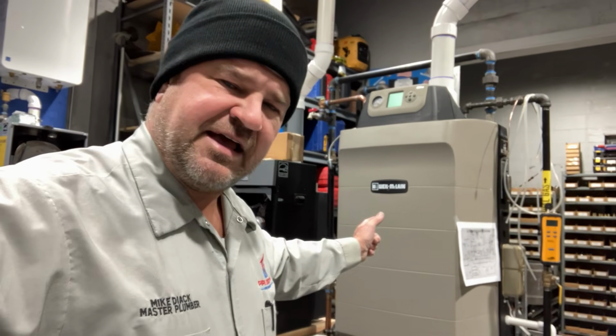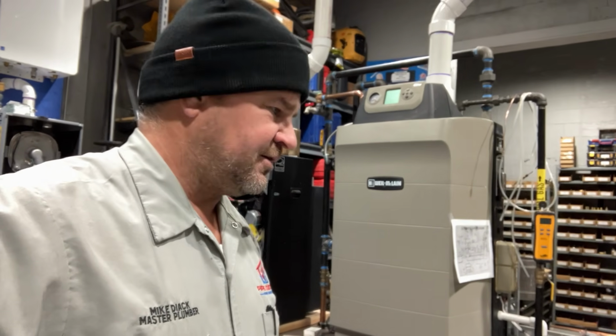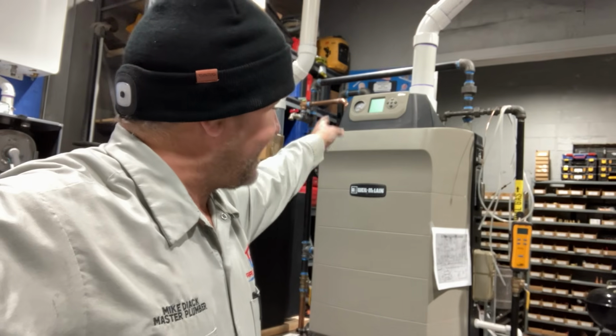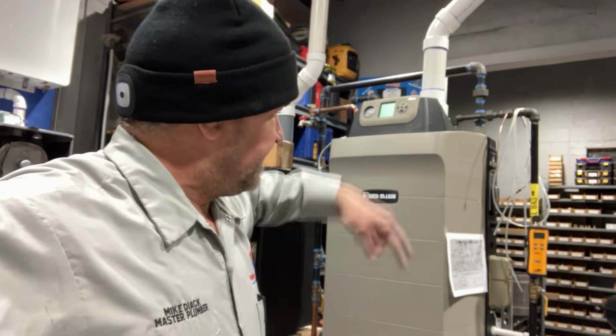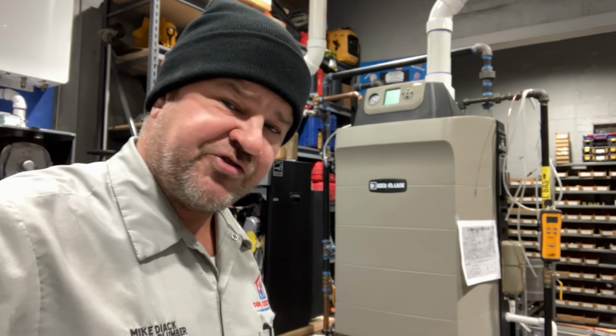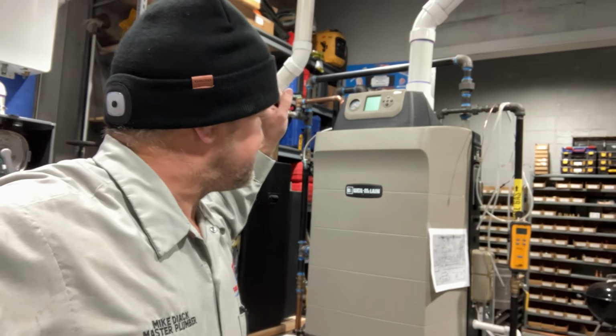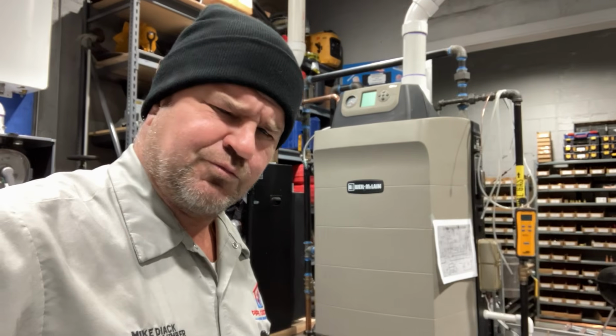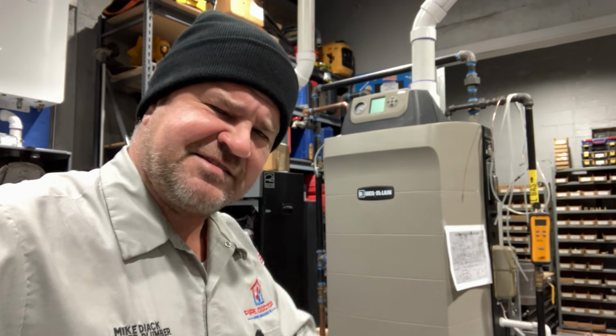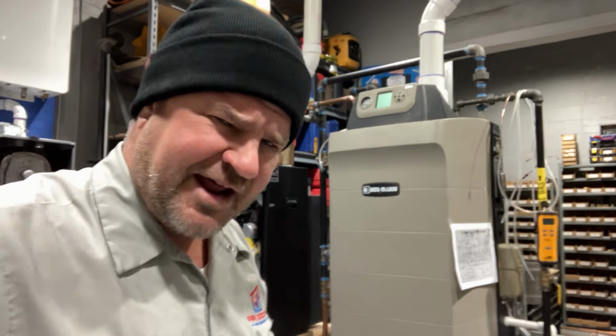I got a Weil McLain Ultra 3. Display is blank. You can hear the draft inducer motor, the blower motor. It's discharging, it's running, but my display is blank. What are we gonna do? Check out this easy fix video on how to get your boiler up and running.